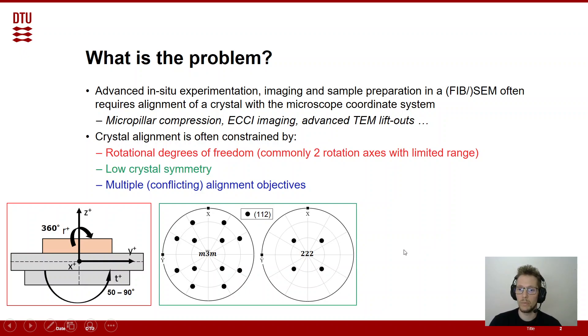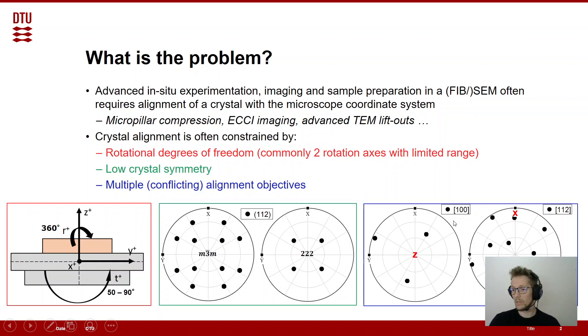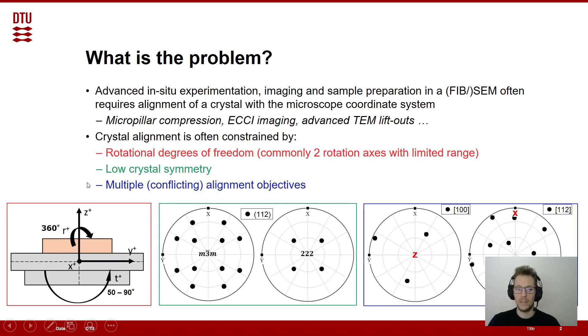This can be quite a constraining factor that makes our alignment more difficult. And of course as soon as we have multiple alignment objectives, this becomes even more difficult — these can even be conflicting. An example of a conflicting alignment objective is shown here: we want to align the 100 direction with the z direction of the microscope and a 112 direction with the x direction of the microscope. Now we know that the 100 and the 112 directions are not perpendicular to each other, but x and z in the microscope are perpendicular. So it is actually an objective that cannot be achieved.